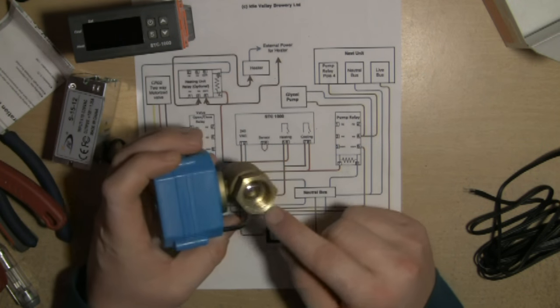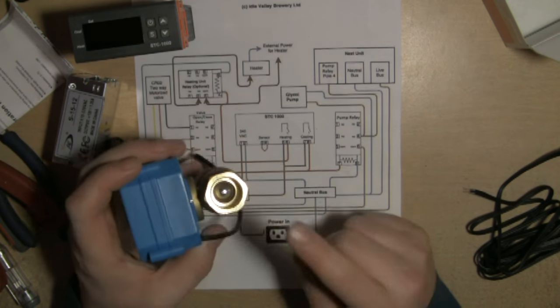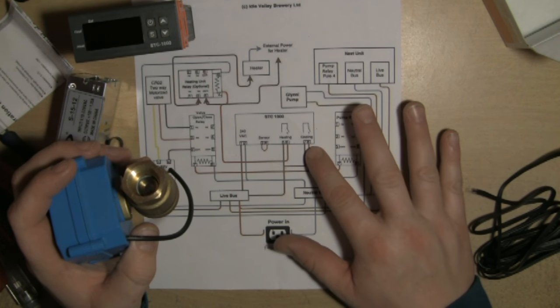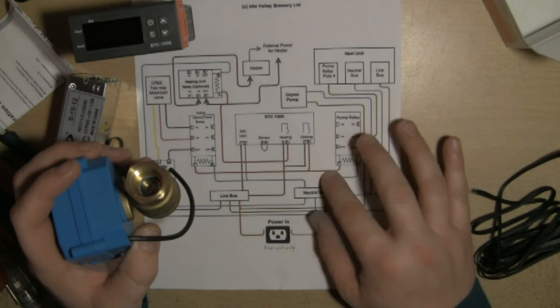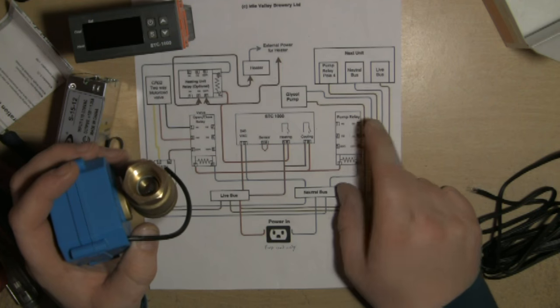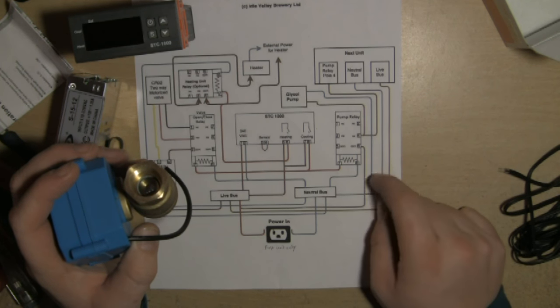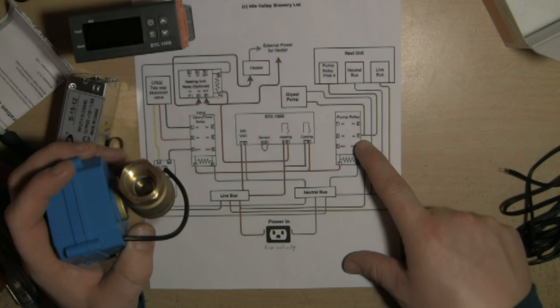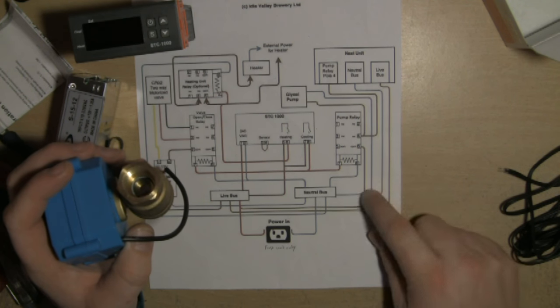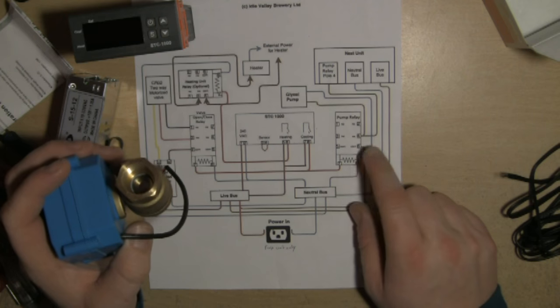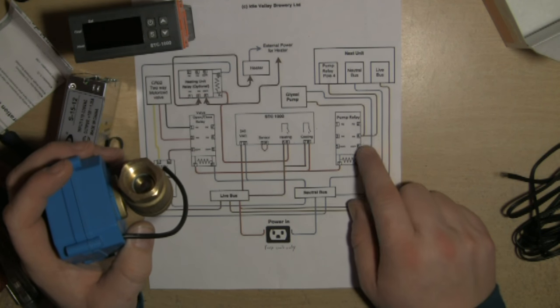The idea is that you also use the power out from the cooling relay to activate the pump relay, which is the glycol pump relay. Then that will allow your live power because all you're going to do is just break the live feed to the glycol pump.